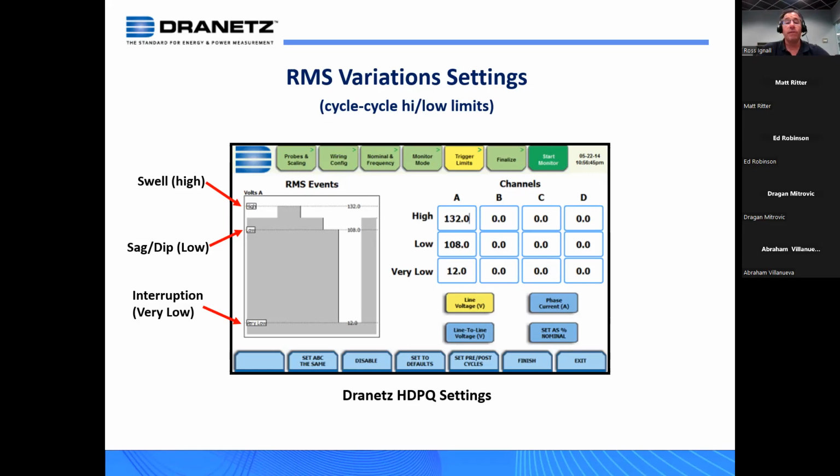very specific application. And the reason being is that the current's always fluctuating, something small to something large, and as your power system goes through its dynamics, it's going to create a lot of triggers. So you need to know really what your loads are and what your application is. They work perfectly fine, but again, be careful what you wish for when it comes to that, because you may get a lot of triggers that you may not expect.